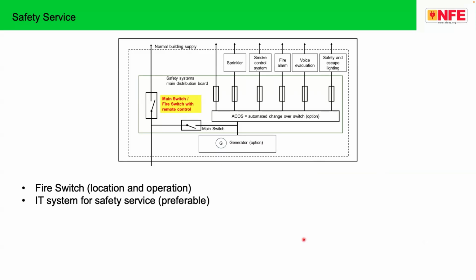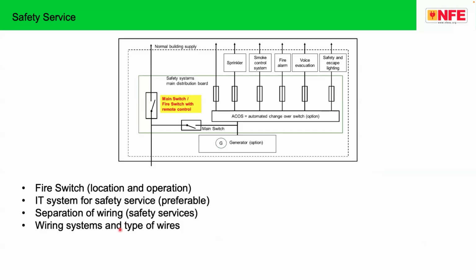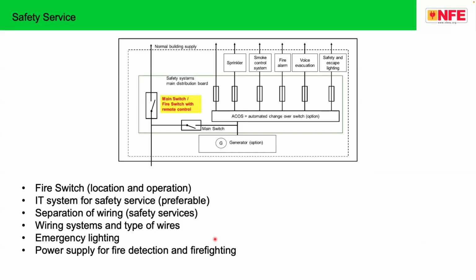The second subject is the IT system for safety services. For safety services, continuity of supply is important, so an IT system can be thought of. Separation of wiring for safety services from the other normal electrical wiring is necessary. Wiring system and type of wires is important. Emergency lighting is important. Power supply for fire detection and firefighting is important.